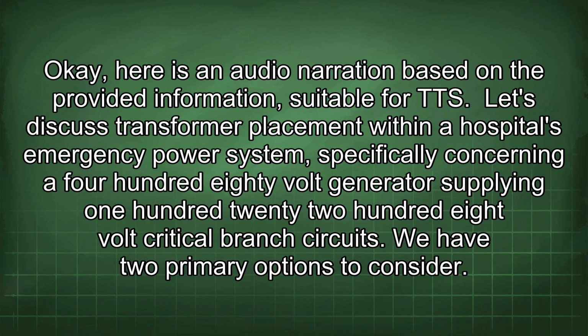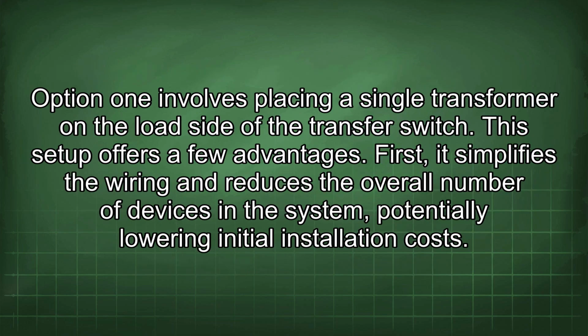Let's discuss transformer placement within a hospital's emergency power system, specifically concerning a 480-volt generator supplying 120/208-volt critical branch circuits. We have two primary options to consider. Option 1 involves placing a single transformer on the load side of the transfer switch. This setup offers a few advantages.